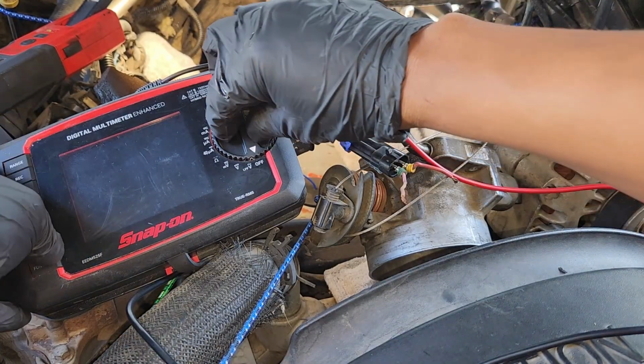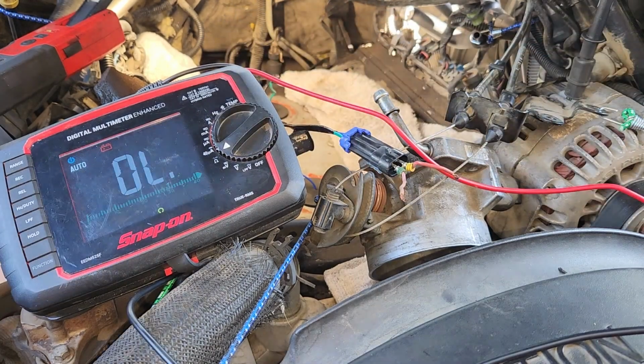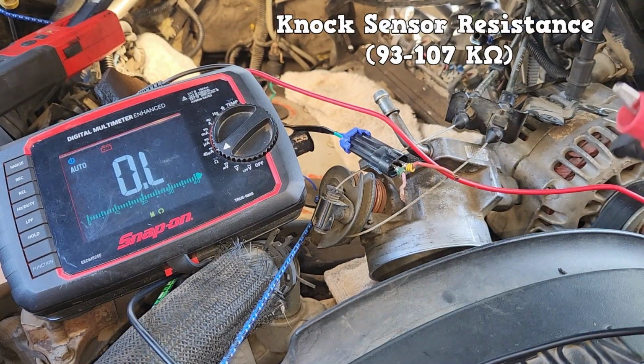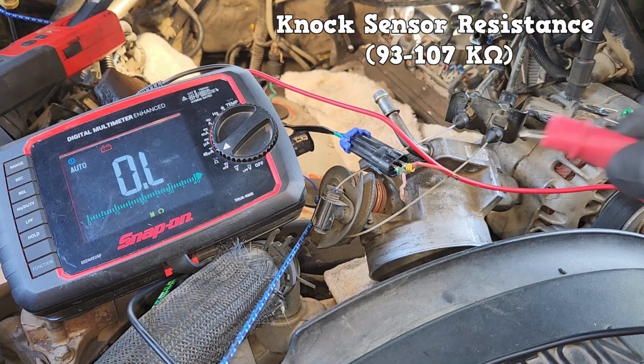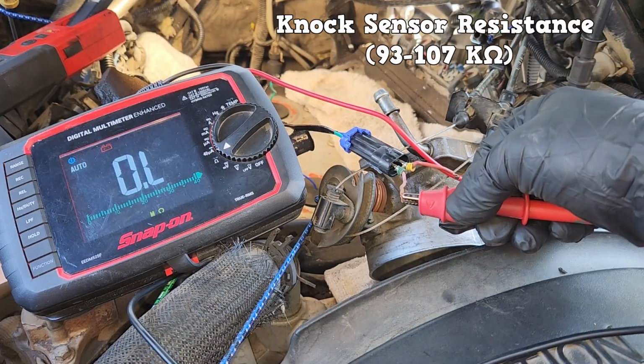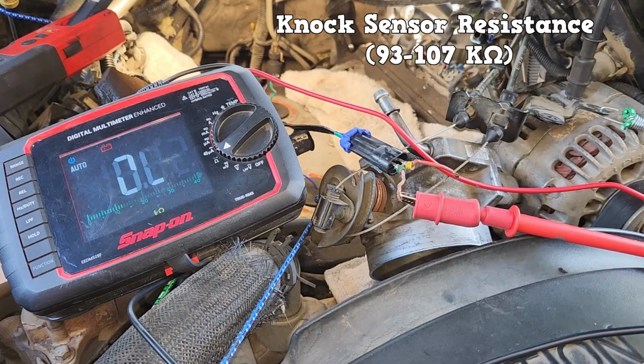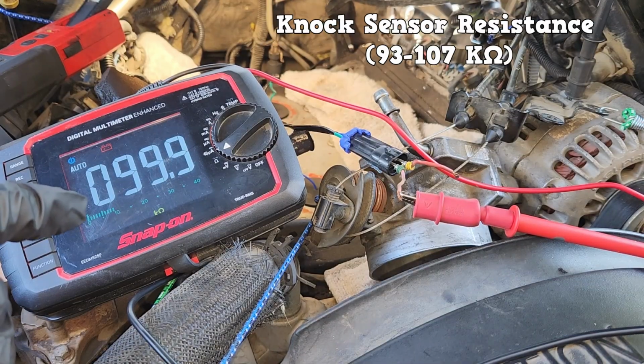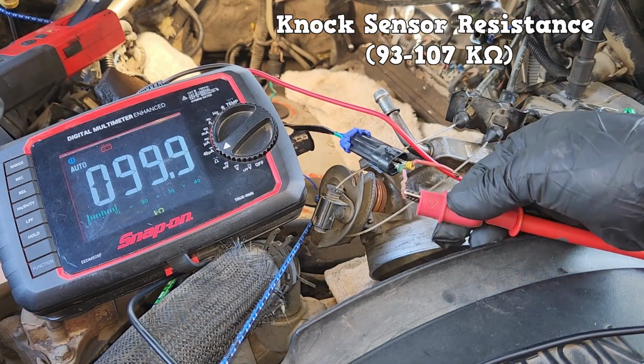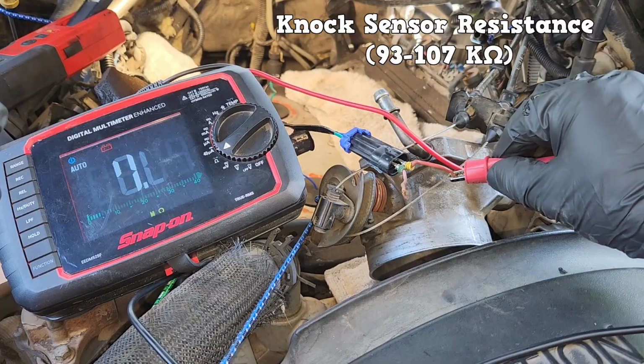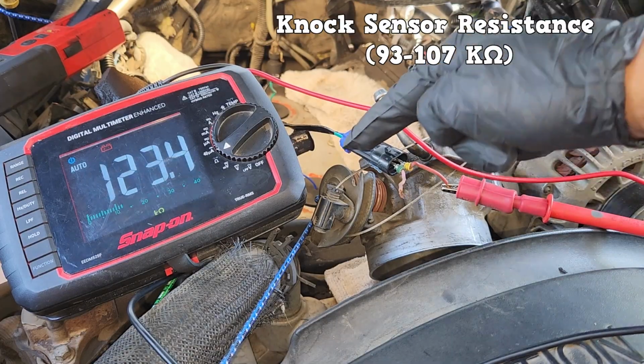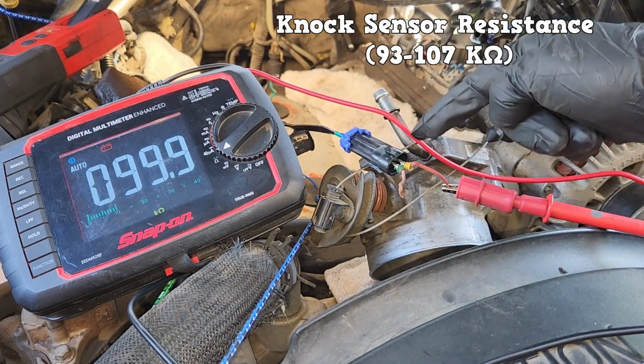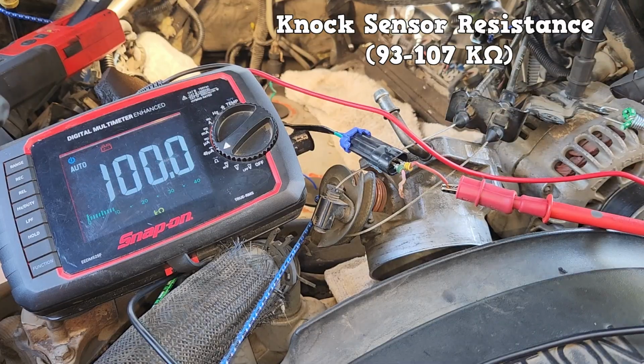Let's go to ohms. The specification here: the resistance should be between 93 and 107 kilo ohms. Sensor number 1 is at 99, within specification. Sensor number 2 was within specifications. Sensor number 1, blue wire, within specifications.